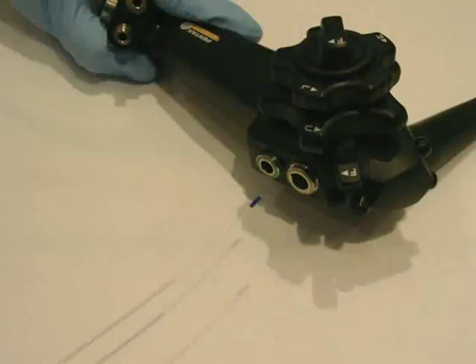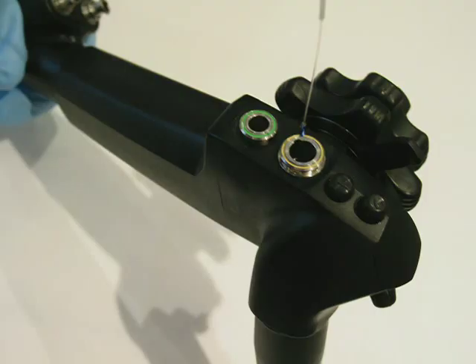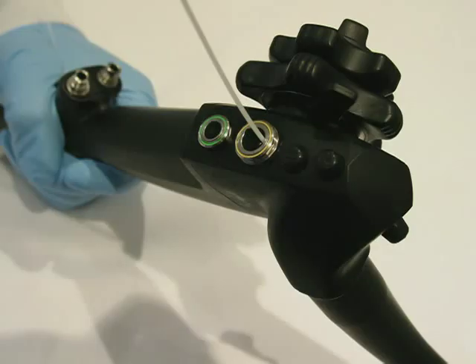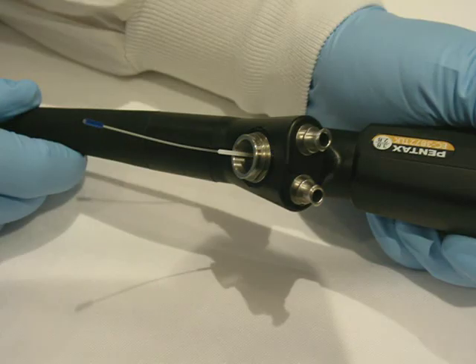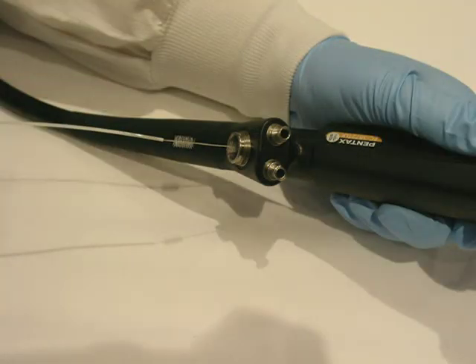Next, insert the blue-coated end of the CS6021T cleaning brush into the opening at the bottom of the suction control valve receptacle on the control head and gently advance until it exits the cylinder of the instrument channel selector. Grasp the back end of the brush shaft, blue end, and then gently pull the brush from the cylinder of the instrument channel selector. Do not use excessive force. Repeat as necessary until the brush is visibly clean.